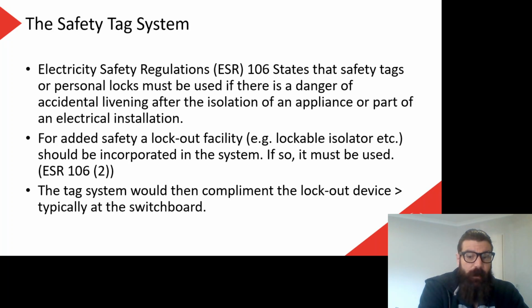For added safety of a lockout facility, for example, a lockable isolator, a lockout facility should be incorporated in the system. If so, it must be used. So that means if we're doing new circuits, particularly with something that's fixed wired, we should have some sort of switch there, a lockable switch, and if it is there, then we should use that. It's better than isolating it back at the circuit breaker. The tag would then complement the lockout device, typically at the switchboard. So again, wherever we've locked that out, we must attach a tag to let everyone know that we have locked it out on purpose, and then not to touch it.